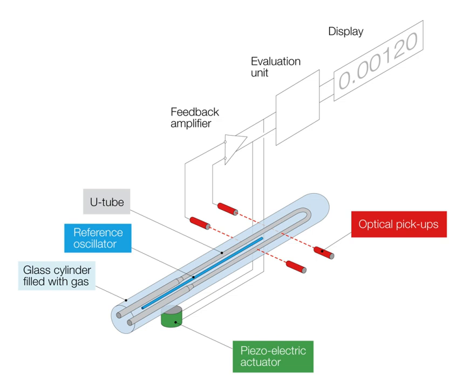The sample is filled into a container with oscillation capacity. The eigenfrequency of this container is influenced by the sample's mass. This container with oscillation capacity is a hollow, U-shaped glass tube which is electronically excited into undamped oscillation. The two branches of the U-shaped oscillator function as its spring elements. The direction of oscillation is normal to the level of the two branches.